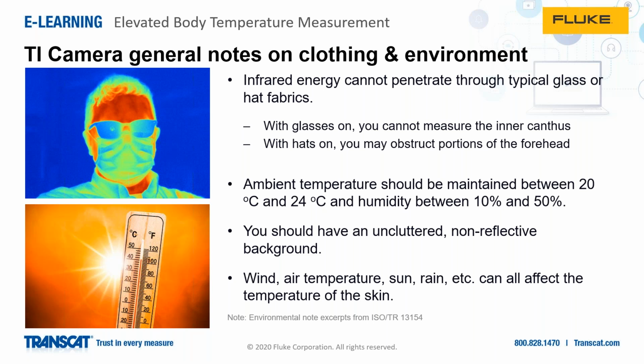Per the ISO TR 13154 standard, the ambient temperature where the camera is being used should be maintained between 20 and 24 C and humidity between 10 and 50%. The background, as we've talked about earlier, needs to be uncluttered and non-reflective so that you don't have stray IR onto the camera from screening an individual.